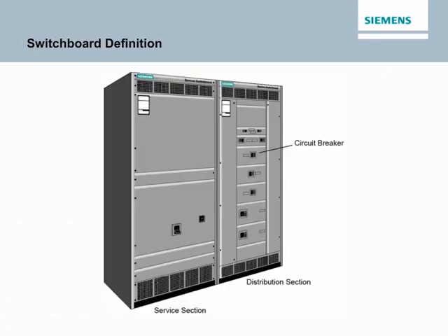The National Electric Code, NEC, defines a switchboard as a large single panel, frame, or assembly of panels on which are mounted on the face, back, or both switches, overcurrent, and other protection devices, buses, and usually instruments. Switchboards may be accessible from the rear as well as from the front and are not intended to be installed in cabinets. As the definition indicates, switchboards enclose various devices.